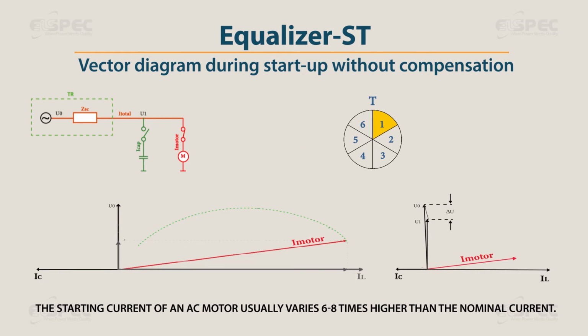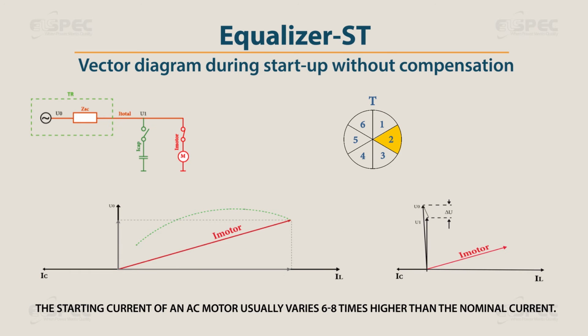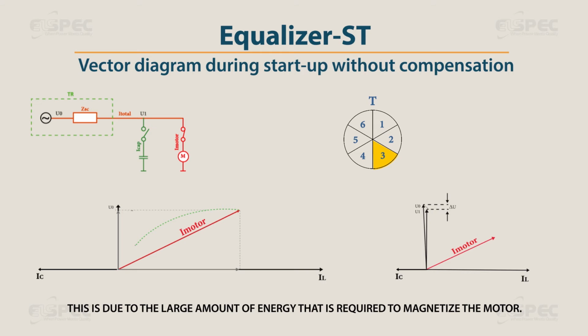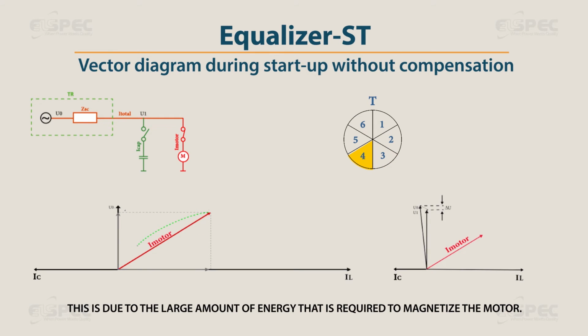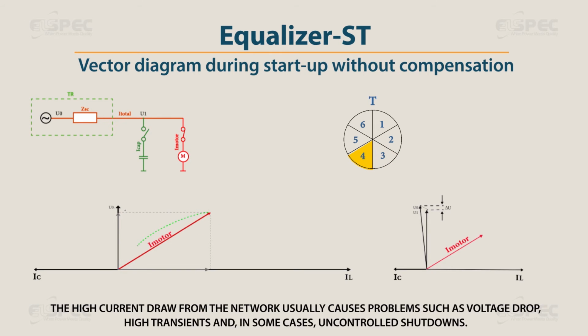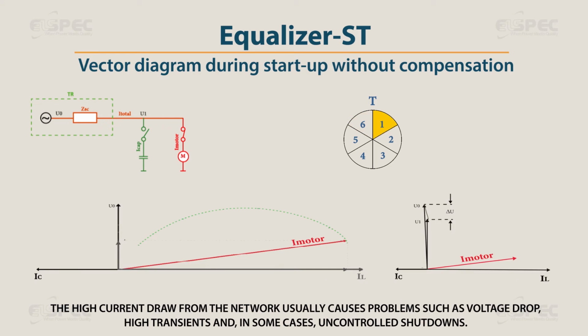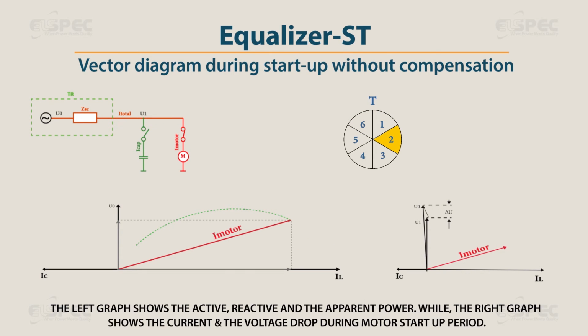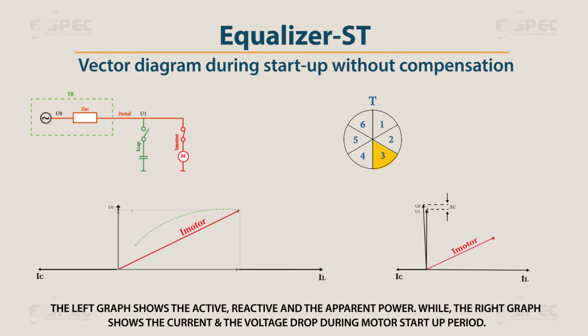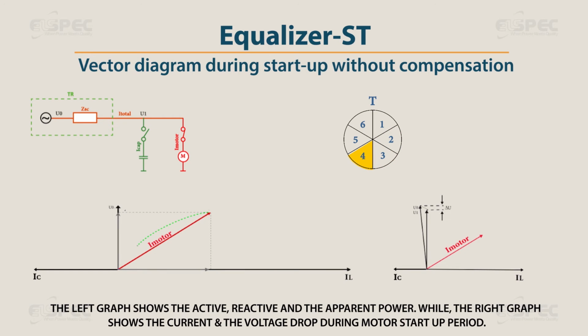The starting current of an AC motor is usually 6 to 8 times higher than the nominal current. This is due to the large amount of energy that is required to magnetize the motor. The high current draw from the network usually causes problems such as voltage drop, high transients, and in some cases, uncontrolled shutdowns. The left graph shows the active, reactive, and apparent power, while the right graph shows the current and the voltage drop during the motor startup period.